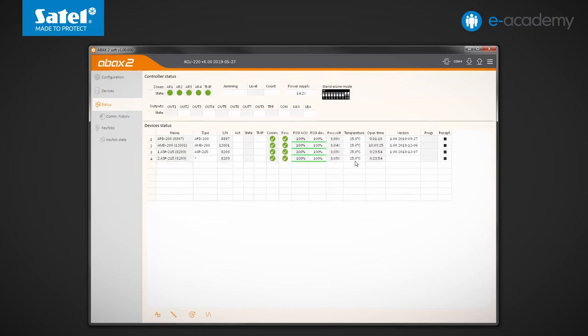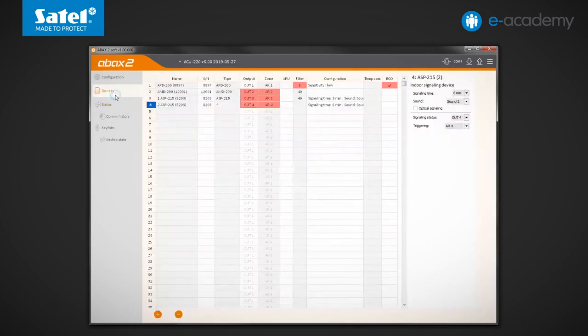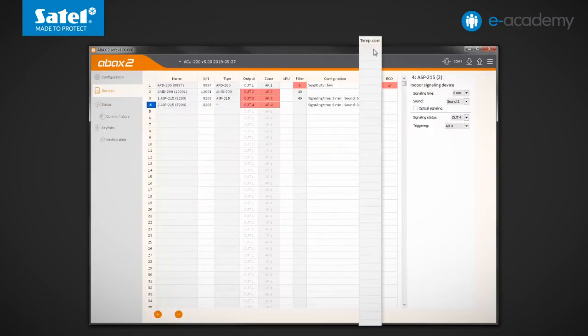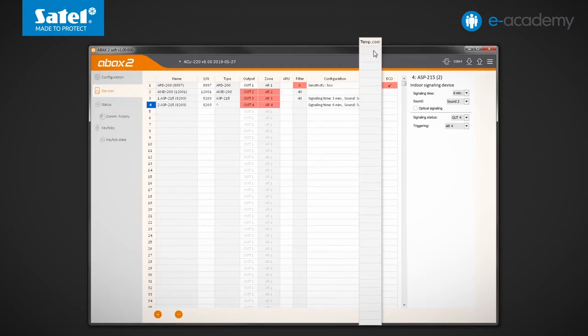If it turns out that the temperature indications should be corrected, then in the column second to last of the device table, you can set a correction ranging from minus 3.5 to plus 3.5 degrees Celsius.